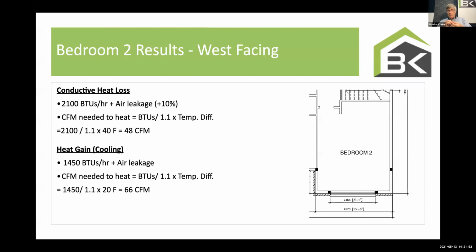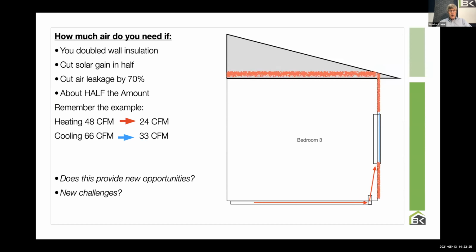So builders and mechanical contractors, if you're not going to do lot-specific, orientation-specific heat loss and heat gains, then you probably need to be doing commissioning and figure it out, because the house on the south side of the street is going to need different airflow characteristics than the house built east-west. So I'm going to put it on builders that if you're going to do high-performance houses, you probably need to be commissioning the HVAC system to set it up for this house built to this specific orientation. And then overall, do yourself a favor, make your houses more efficient. And now it's far less problems getting heat out to those specific rooms or specific areas.